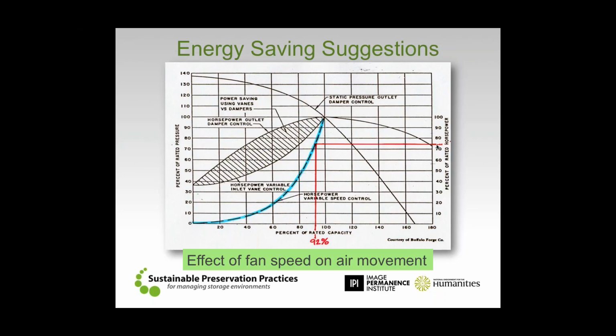Well, what if I can go a little bit further and let's say I find out that during the night or in wintertime, if I send 50% of the total air into the space, I can still maintain conditions. Well, here we are. We'll take it a little bit further down, and if I run that fan at 50% and send 50% of the total air in, we've just saved 90% of the total energy consumption. That's a pretty darn good payback. If we can run a space with 50% of the total quantity of air and still maintain conditions and save 90% of the energy that it takes to do that, that's kind of a no-brainer.